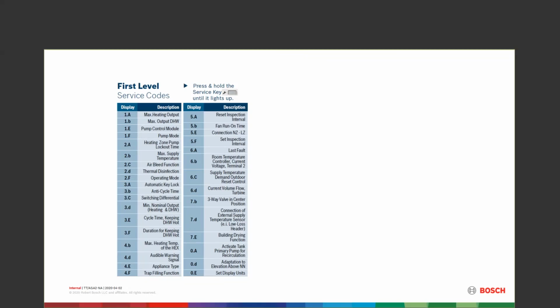3B is an anti-cycle time that shortens things up or lengthens them out. So you can have a longer differential or a shorter differential. Cycling time, and then your switching differential can go from anywhere from 1 degree up to 18 degrees.